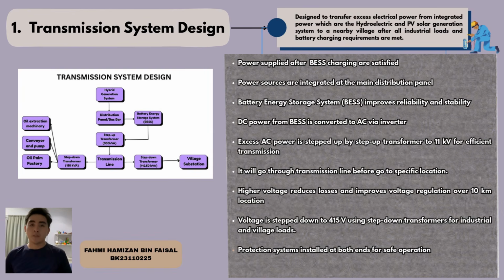Since the BESS produces DC power, an inverter will convert it to AC. A step-up transformer increases the voltage to improve transmission efficiency. Higher voltage reduces losses over the 10 km distance. Before reaching the factory and village, a step-down transformer reduces the voltage to safer levels. Lastly, protection systems are also installed at both ends for safe operation.